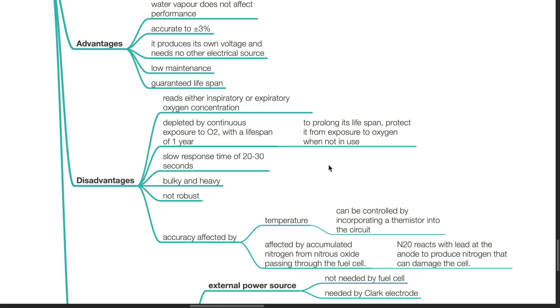Further disadvantages: it has a slow response time of 20 to 30 seconds, it is bulky and heavy, not robust, and accuracy is affected by temperature, which can be controlled by incorporating a thermistor into the circuit. It is affected by accumulated nitrogen from nitrous oxide passing through the fuel cell, as nitrous oxide reacts with the lead anode to produce nitrogen that can damage the cell.